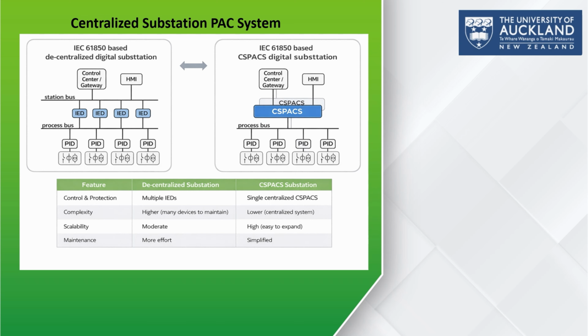Field devices such as circuit breakers, transformers, and sensors are connected to protection and instrumentation devices. In short, we call them PIDs, which in turn communicate digitally via the process bus to the IEDs. In this setup, data flows from field device to PIDs, then IEDs, and finally to the control center. While this decentralized structure offers flexibility, it increases complexity because each IED must be individually configured and maintained.